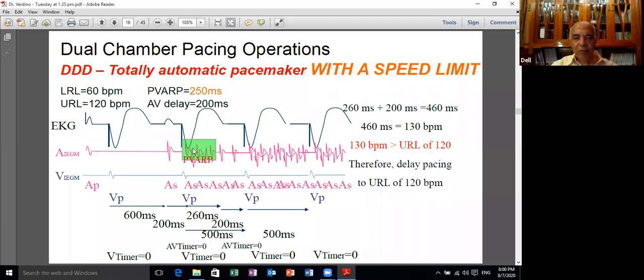But here the person went into atrial fibrillation. It's unphysiological to sense the atrial fibrillation during the PVARP, the post-ventricular atrial refractory period. So here it's conducted, and it lasts 250 milliseconds. Nothing is sensed because this is blanked out. Immediately after the 250 milliseconds, we started to sense the fibrillation waves. So at 260 milliseconds, the atrial electrode sensed the fibrillation waves. So it's going to count from here 200 milliseconds, which is the AV delay, and throw a spike.